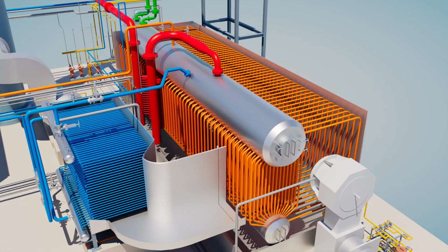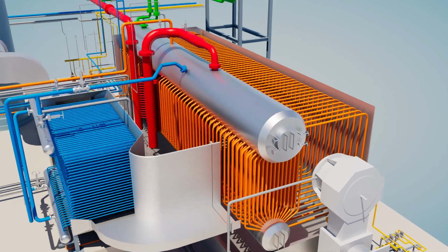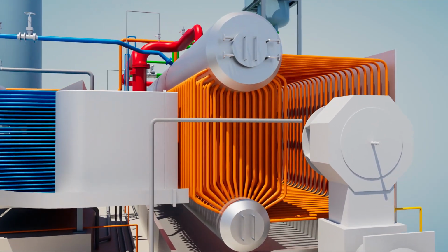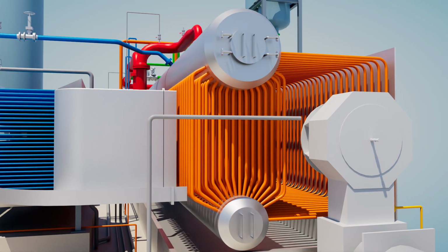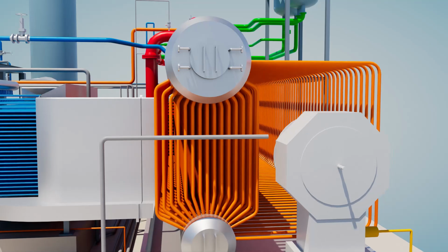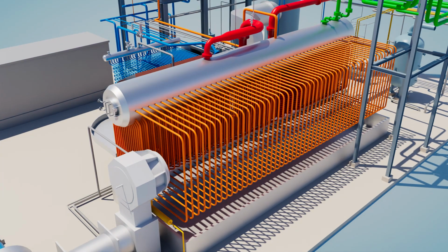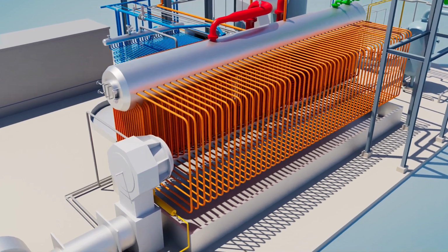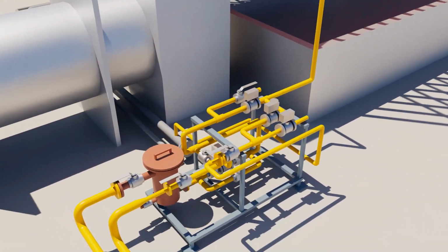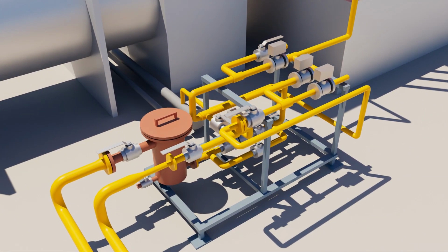The auxiliary boiler's water drum is located at the bottom of the water tube boiler, while the steam drum is located at the top. Furnace. Closely spaced water wall tubes form the membrane walls at the side, roof, except for burner opening, rear, and front of the furnace.